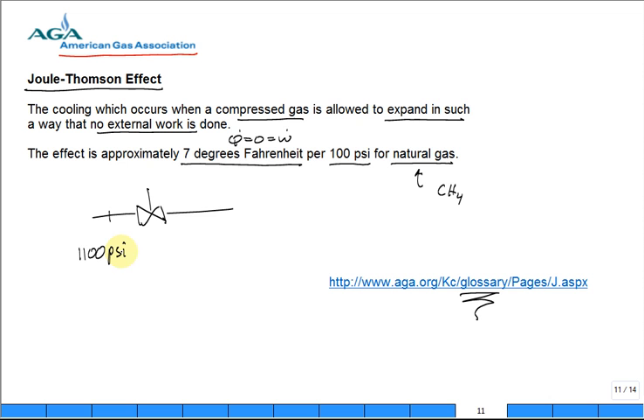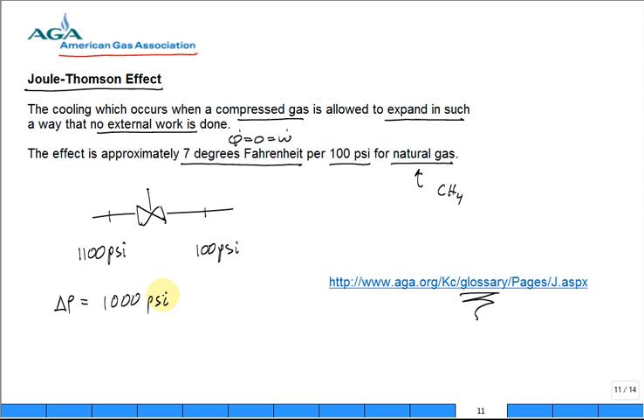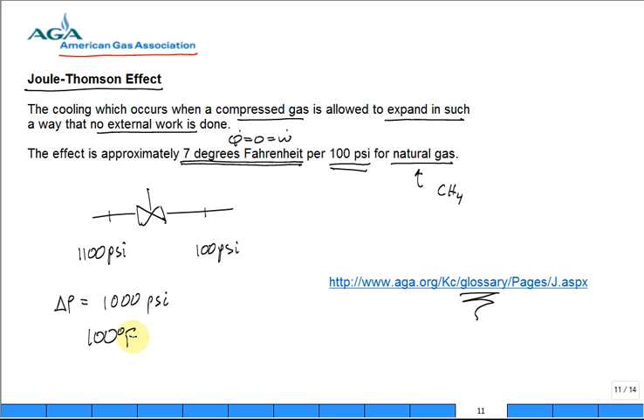Maybe you come in here with 1100 psi and it drops down on the backside of the valve to 100 psi, all reasonable pressures. What's the Delta P? It's a thousand psi pressure drop. They say there will be a seven degree Fahrenheit drop for every 100 psi pressure drop.